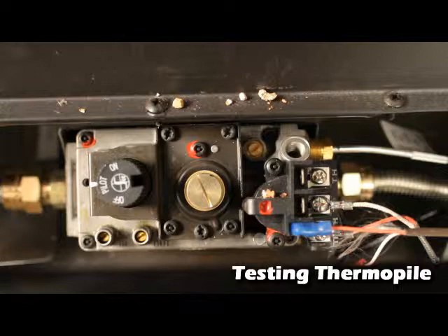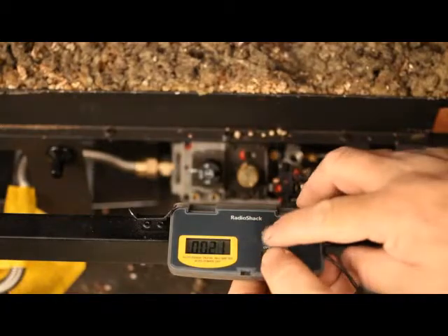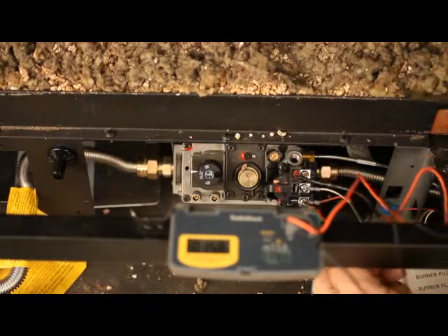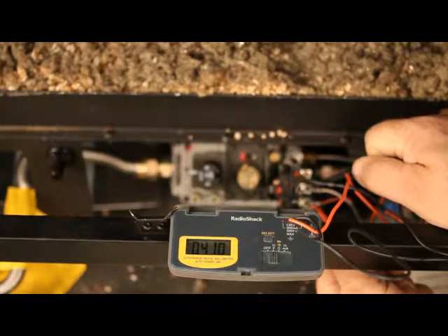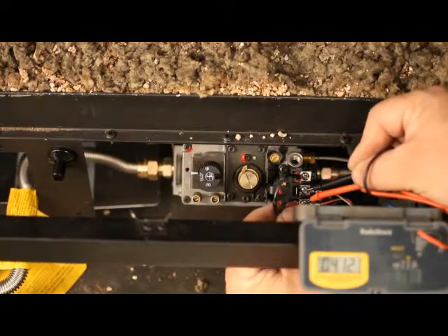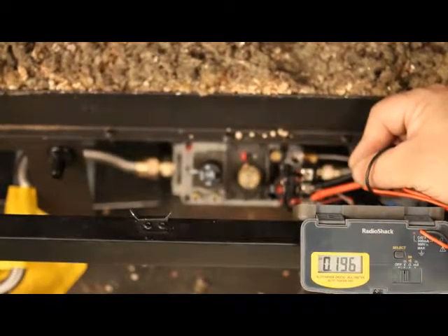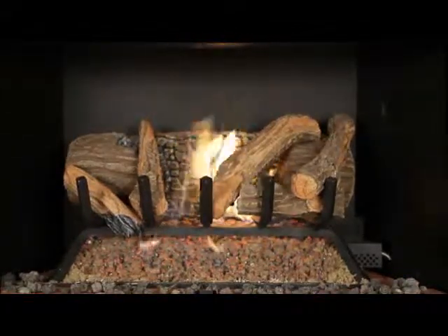Testing the thermopile. With the pilot lit and the burner off, set your multimeter to the DC setting or millivolt setting. Place one probe on the terminal THTP, the other probe on the terminal TP. Millivolts generated should be 325 minimum; generally readings will be 400 to 700 millivolts. Record your readings. Keep the probes on the terminals and turn the appliance on. Millivolts will typically drop in half — 150 millivolts generated should be the minimum; generally readings will be 180 to 280 millivolts. With the burner on, recheck millivolts every 5 minutes until they have held a steady reading and are not dropping. Record all your readings with the time recorded also.